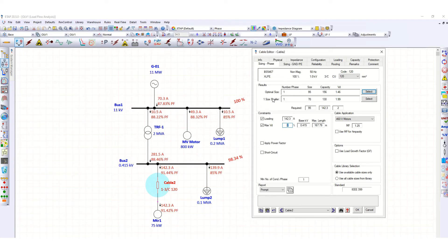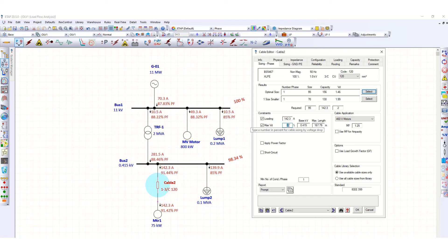The software also recommends one size smaller — single core 70 square mm with a capacity of 130 ampere — but since the load requirement is 142.3 ampere, we should not select this one. Also, the voltage drop is almost 2%, so we should avoid this size and select single core 95 square mm instead.